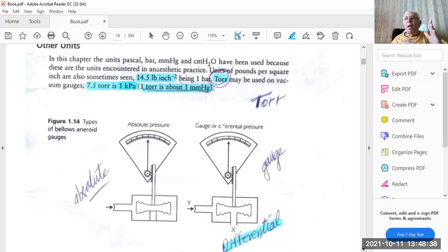The two openings are controlled by two pressures. Suppose I want to take a difference reading between both pressures. I apply pressure at each point, and the end result will yield the final pressure. We call this differential pressure transduction. The one on the left is completely absolute because it's not attached to the atmosphere, whereas the one on the right is attached to the atmospheric pressure, so we can call it a gauge pressure and not an absolute pressure.